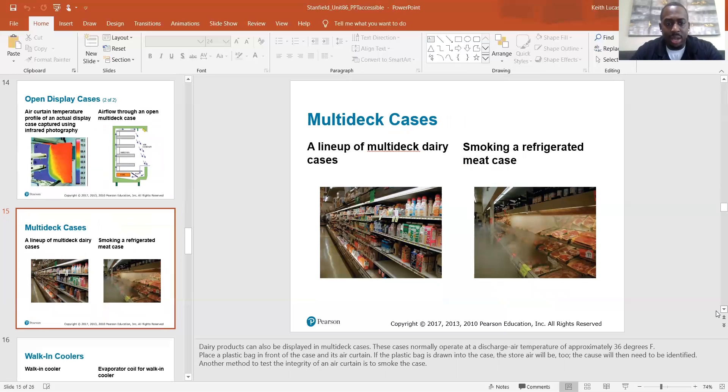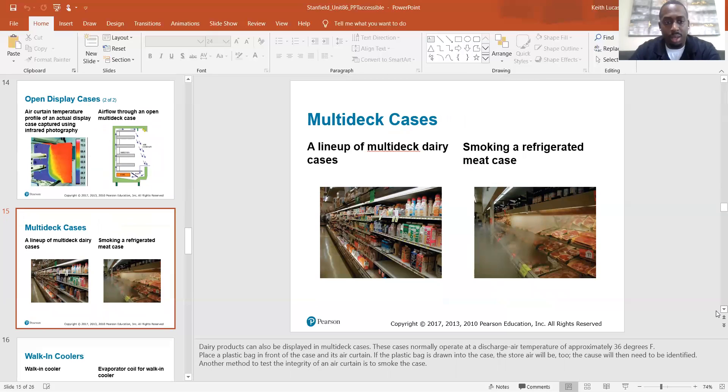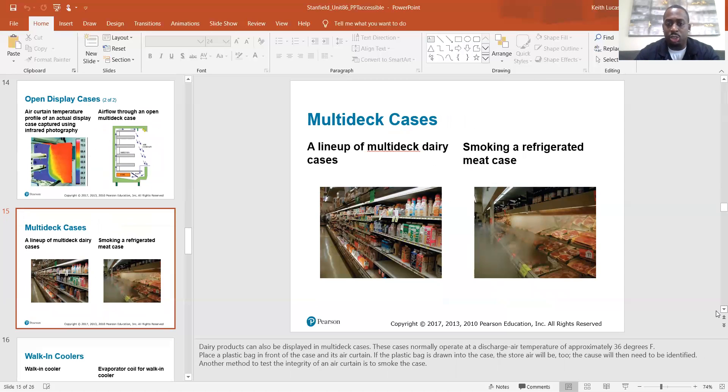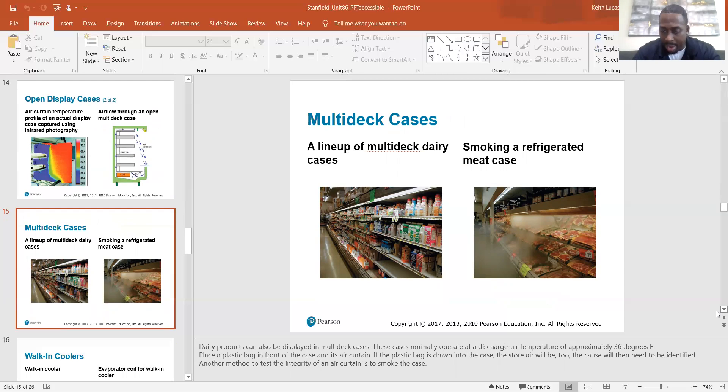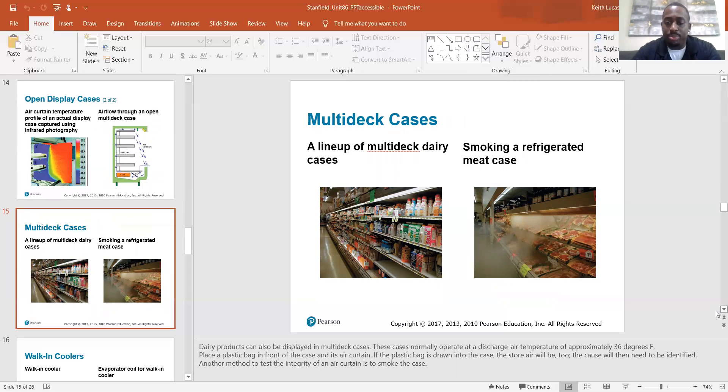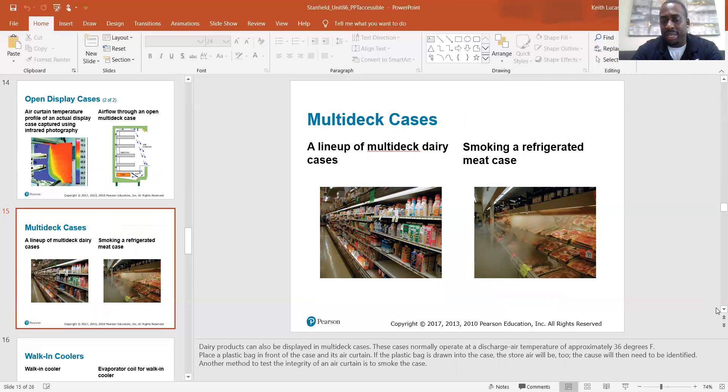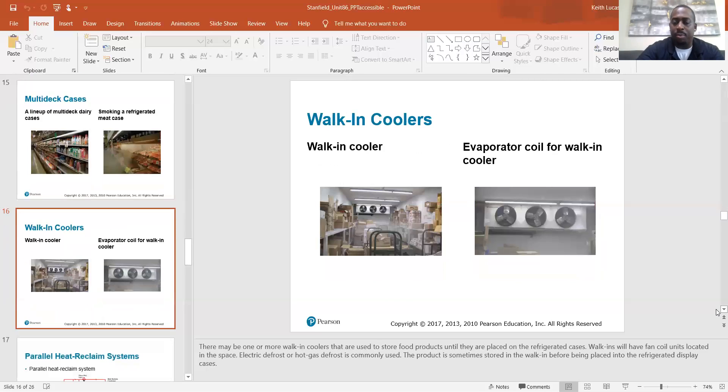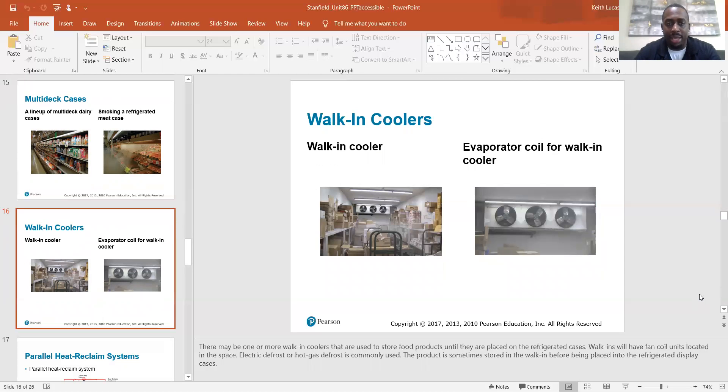So dairy products can also be displayed in multi-deck cases. These cases normally operate at a discharge air temperature of approximately 36 degrees Fahrenheit. Place a plastic bag in front of the case and its air curtain. If the plastic bag is drawn into the case, the store air will be too. If the plastic bag can get sucked in, then the hot air in the store also can get sucked in. The cause will then need to be identified. Another method to test the integrity of the air curtain is to smoke the case. So basically, if we can draw things in to the case, then we know our air curtain is not operating properly. We need to figure out what's going on. Is it a fan issue or what the problem actually is.